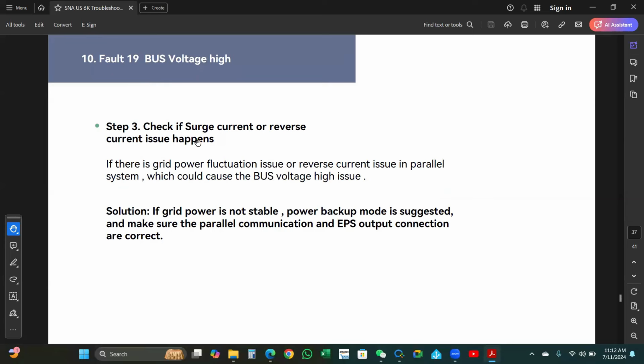Step 3. Check if a surge current or reverse current issue happens. If there is a grid power fluctuation issue or a reverse current issue in the parallel system, it could cause the bus voltage high issue. Solution: if the grid power is not stable, power backup mode is suggested, and make sure the parallel communication and the EPS output connection are correct.